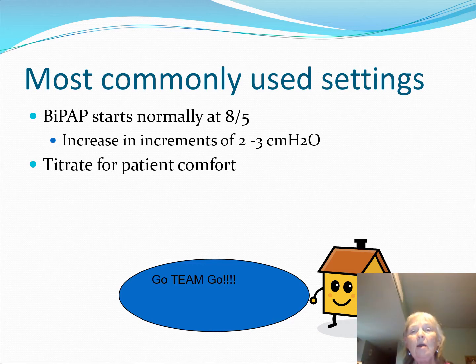No way. And so instead of starting at 8, we'll sometimes lower it to 6. And then we'll see if we can get them to start at 6. If they can't, we'll have to lower them both to 5. EPAP in some cases does not go below 4, and neither does the IPAP, and we'll just bring it down to that level. And then if we can at least get them to put it on, feel how it feels, make them comfortable with it, then we can start to increase those numbers closer back to where the physician ordered them, okay?